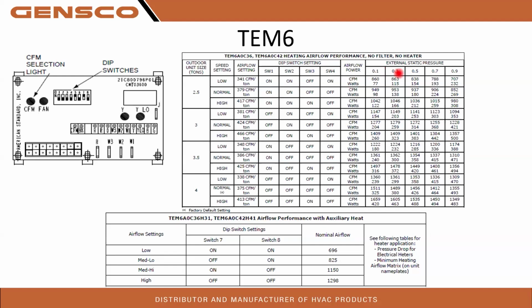Let's look at this 3-ton, at the CFMs over here. You got 1147, 1149, 1141, 1123, and so on if you're on low speed, right? See how as the static goes up, the airflow stays pretty good, but your wattage goes up. That's why the true ECM variable speed motors can overcome marginal ductwork, but they can't overcome bad ductwork. And that's just what I wanted to point out on these charts: the true ECM will try to keep the airflow up, and the motor will ramp up through the internal torque, amperage, and RPM calculation that it makes. And that's all I wanted to mention.